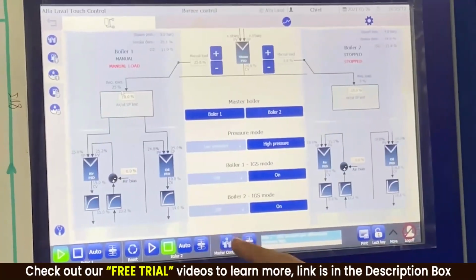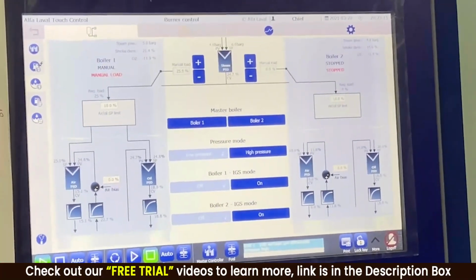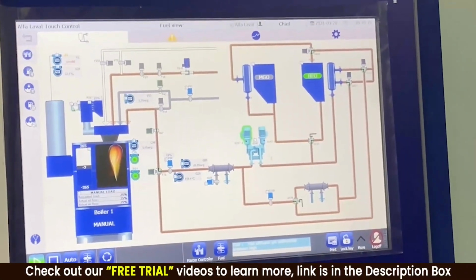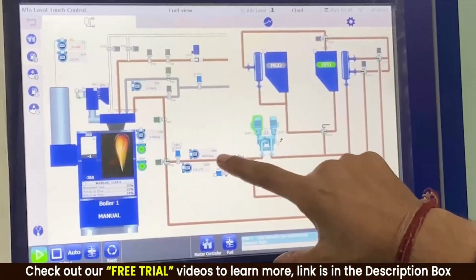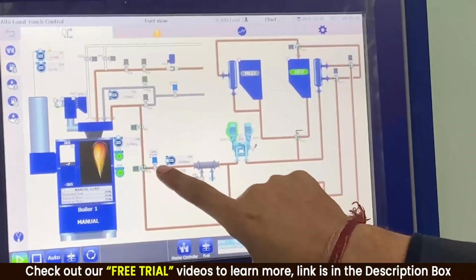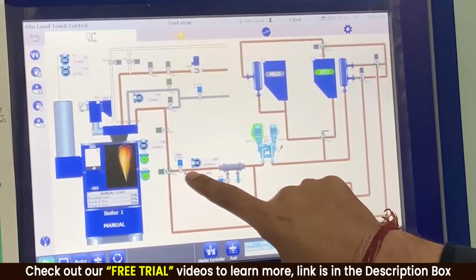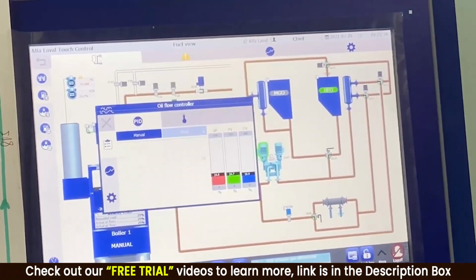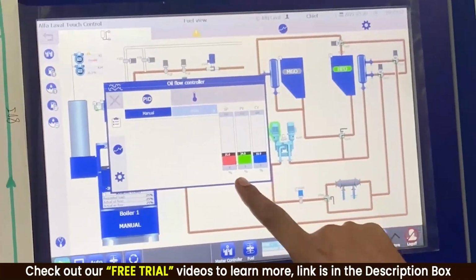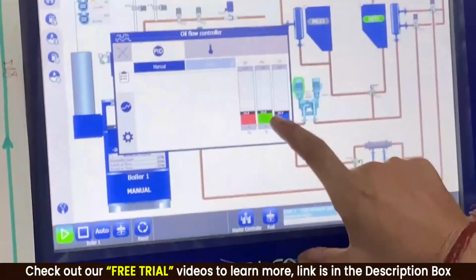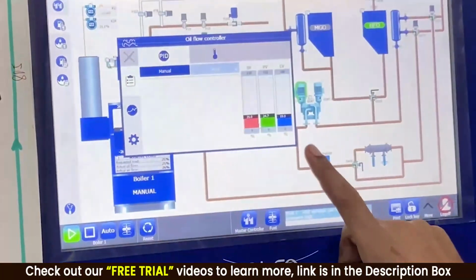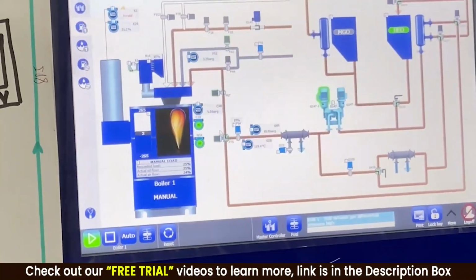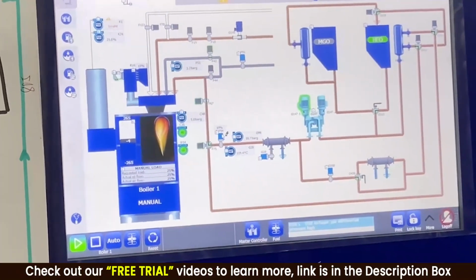And this goes to this valve over here. See, this is the pump running through the heater, through the pressure transmitter and temperature transmitter. This is the fuel oil regulating valve, the boiler fuel oil regulating valve. So I open this valve, and what I see is that it has a controller. Set point is 25%, guys, right? We are running 25% load. Measured value is 24.8%, and control output is 19%. So this valve is actually now 19% open. You can see over here, right guys?